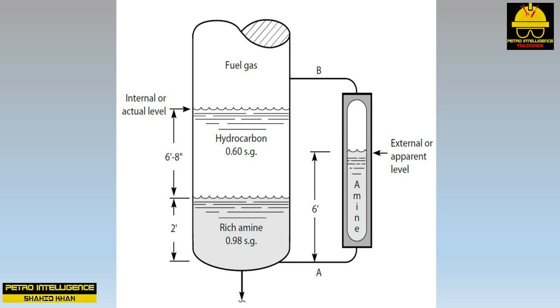This discrepancy between the apparent level in the gauge glass and the actual level in the tower also occurs in any other type of level measuring device, including external float chambers, displacement chambers, and level trolls. The one exception is level measuring devices using radiation techniques. The three causes of this discrepancy are: foam formation inside the tower, ambient heat loss from the external gauge glass or level troll, and the liquid specific gravity in the glass being greater than in the tower.